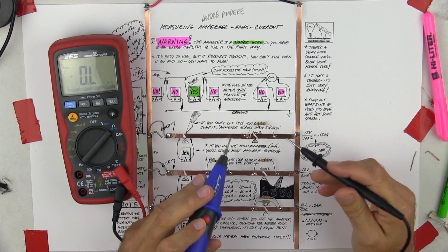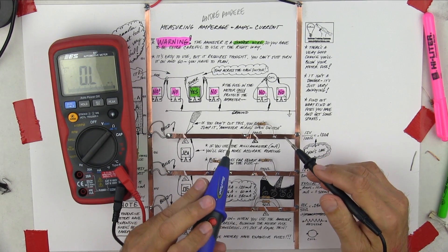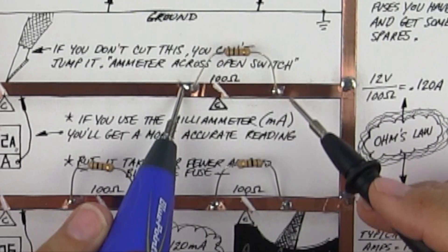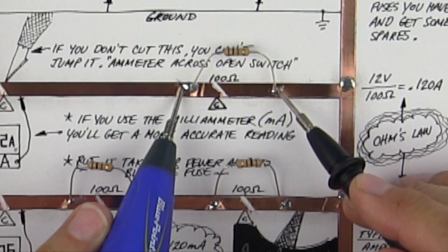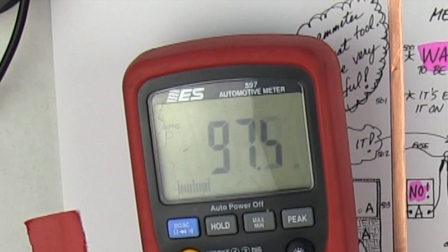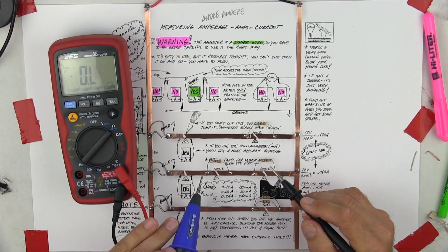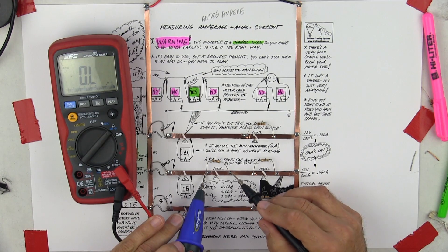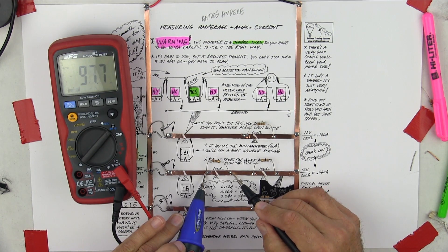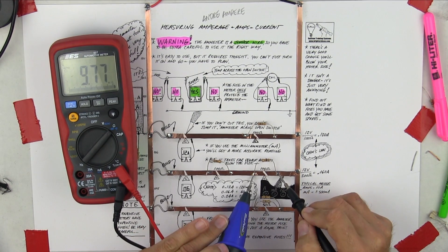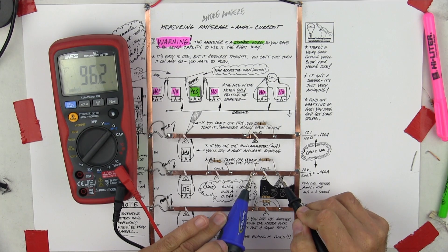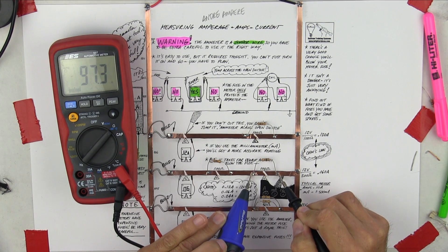So if you're trying to diagnose, you don't want to work with wrong answers. So if I did this right, I should read here. I should read about 100 ohms, and I'm at 97.4. If I read here, I should read 100. If I read here, I should read 100, roughly, plus or minus. They're averaging at about 97.